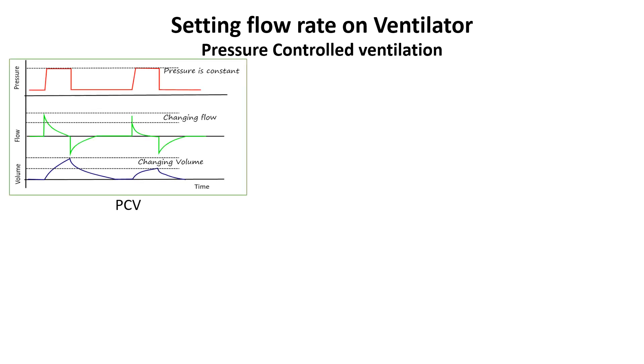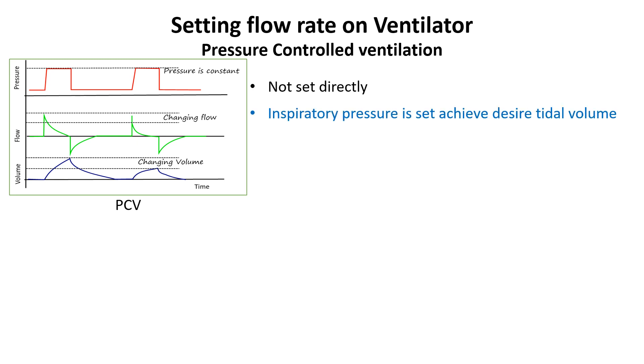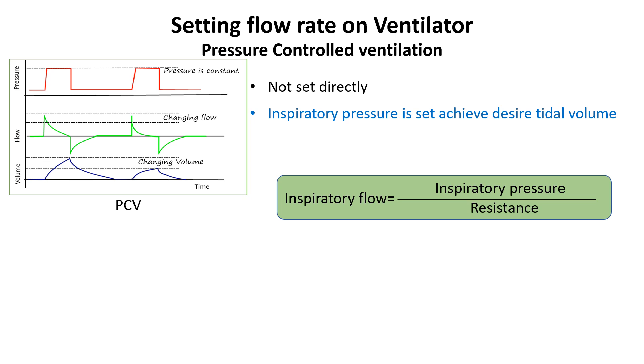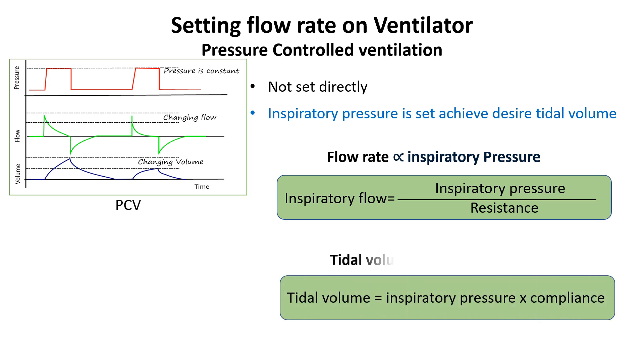In pressure-controlled ventilation, flow is not set directly. Instead, inspiratory pressure is used to achieve the desired tidal volume. Increasing the inspiratory pressure increases the pressure gradient between the ventilator and the lungs, leading to higher flow. Conversely, lowering inspiratory pressure reduces the pressure gradient, resulting in lower inspiratory flow. Tidal volume also increases but depends on lung compliance.